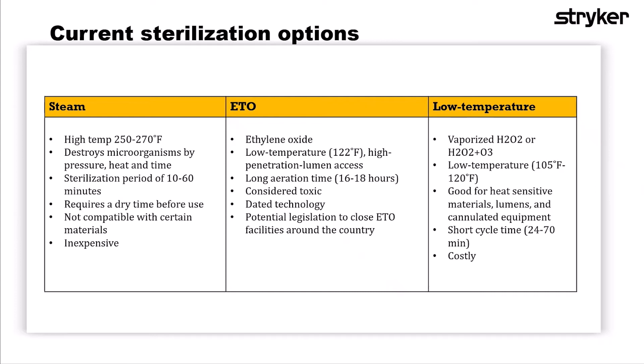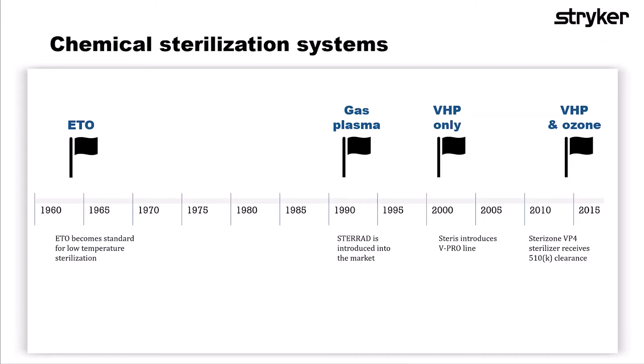Vaporized hydrogen peroxide sterilization has a relatively short cycle, anywhere from 24 to 70 minutes. However, it is quite costly. Looking at the timeline, ETO was used as early as the 1960s for sterilization. The first low-temperature sterilizer we saw come out in the 1990s was STERRAD, using vaporized hydrogen peroxide with plasma. Then STERIS introduced their V-Pro line in 2000 using vaporized hydrogen peroxide only. Around 2012-2013, the Stryker Sterizone VP4 was introduced, utilizing vaporized hydrogen peroxide with ozone.